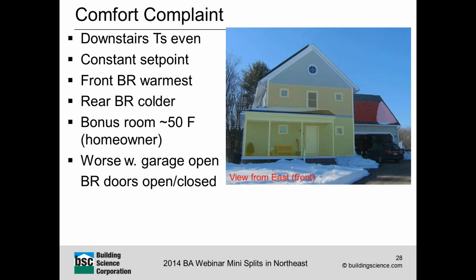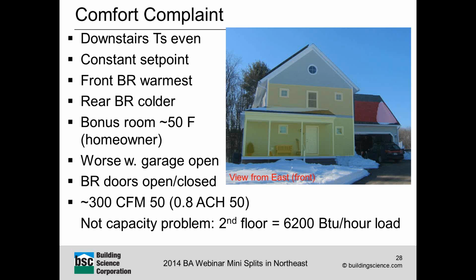So the first thought was, is this an airtightness problem? We retested that, running at under 1 ACH50, very nice and airtight. And it's definitely not a capacity problem either: that second floor had a 12,000 BTU per hour head, while the design load at design winter conditions for the second floor is about 6,000.